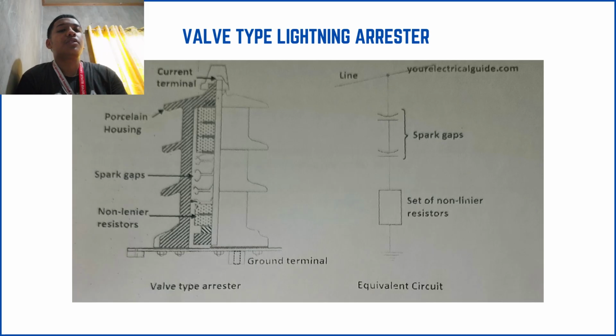Under a normal condition, they provide insulation and prevent current from flowing. However, during a lightning surge, the voltage rises and the spark gaps break down, allowing the surge current to pass through the nonlinear resistors to the ground. This nonlinear resistor, usually made of silicon carbide or zinc oxide, limits the voltage across the equipment by allowing more current to flow as the voltage increases. This is what keeps the system safe.